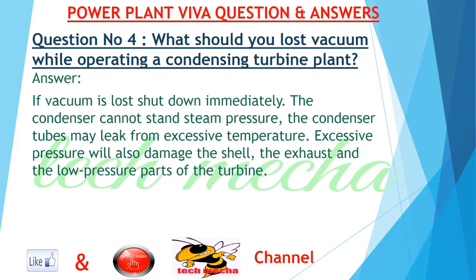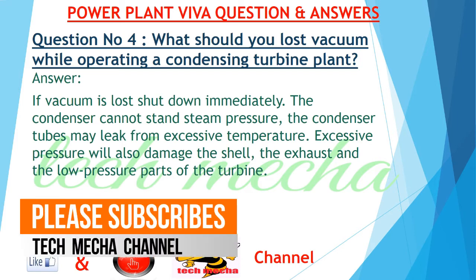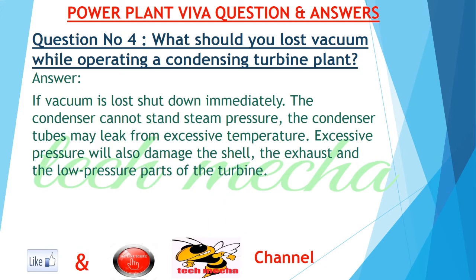Question number 4: What should you do if you lose vacuum while operating a condensing turbine plant? Answer: If vacuum is lost, shut down immediately. The condenser cannot stand steam pressure; the condenser tubes may leak from excessive temperature. Excessive pressure will also damage the shell, the exhaust, and the low pressure parts of the turbine.